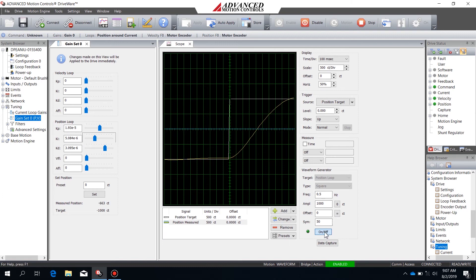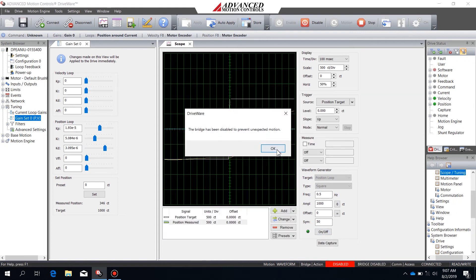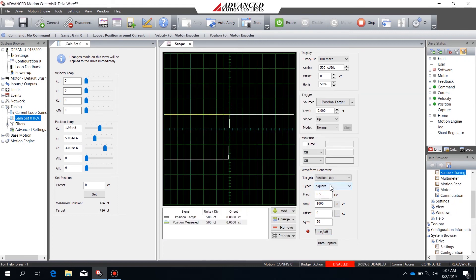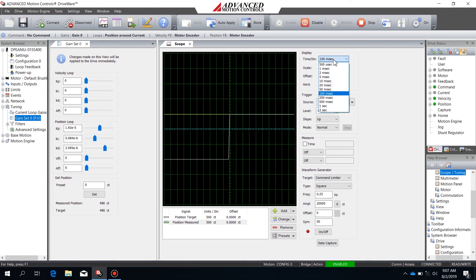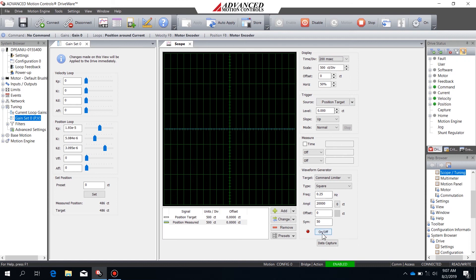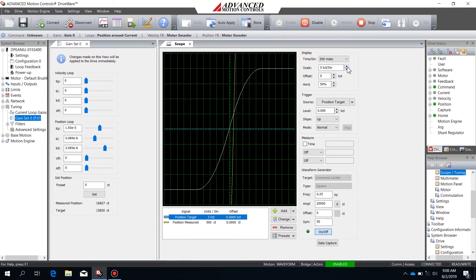I'm going to disable the current waveform and change my target to the command limiter. I'll start by reducing the frequency to a quarter hertz, zero the offset, and set the amplitude to 20,000 counts. When I enable the bridge, I'll increase the time per division so I can see the whole wave and the point where it's sitting at zero velocity. I'll also need to increase the units per division so the trace doesn't go off the screen.